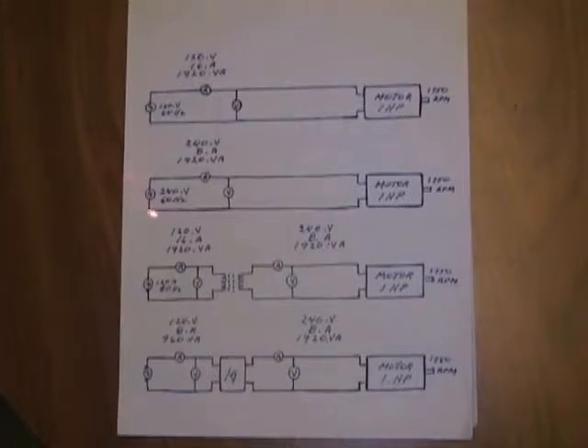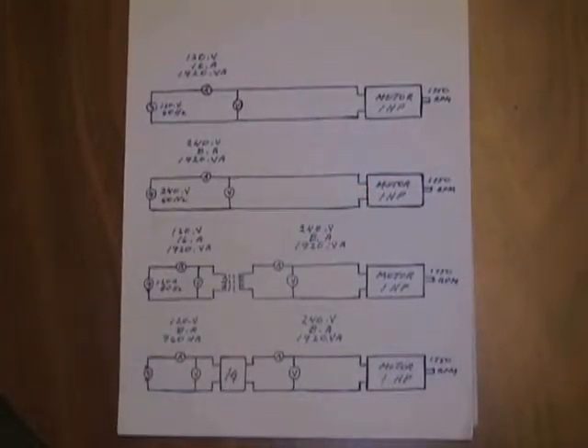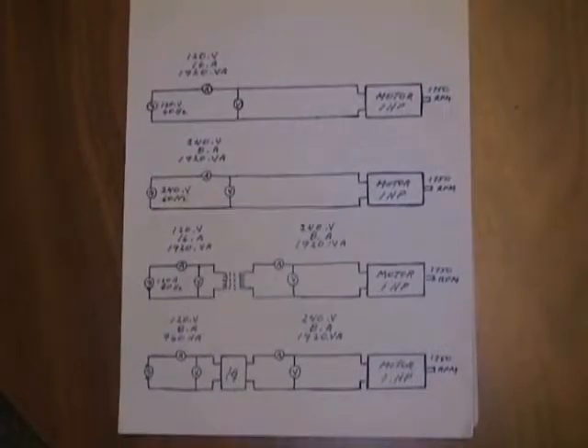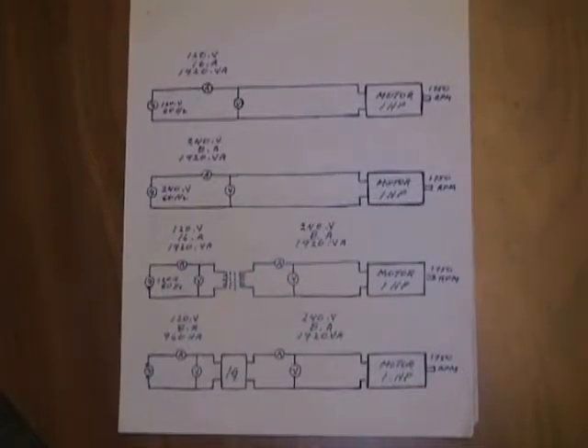The second drawing is the same motor running at the same RPMs, but now it is connected at 240 volts and 60 hertz. The motor is connected in the high voltage form, and it will require 240 volts, 8 amps, and it will require the same amount of volt amps, which is 1920, just like the 1920 of the first drawing.